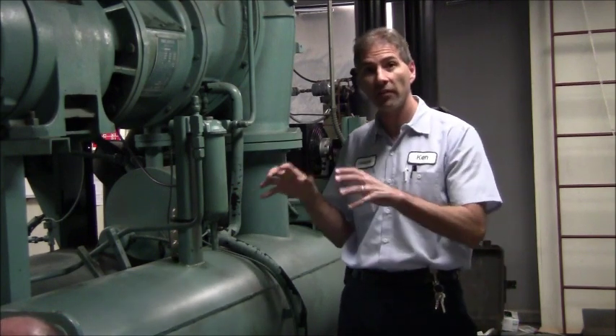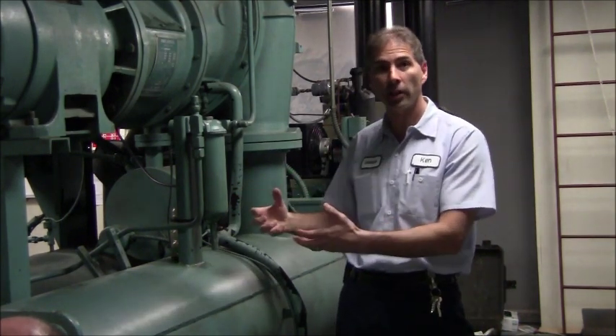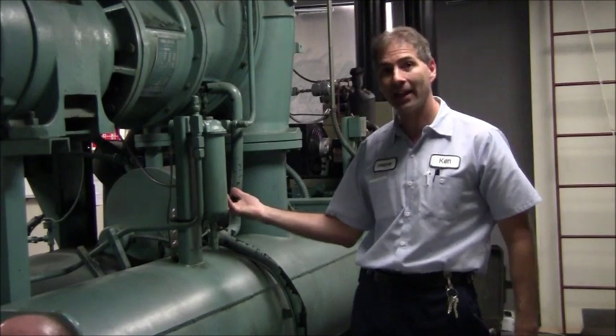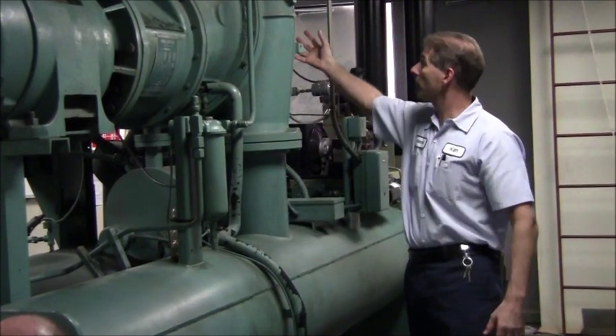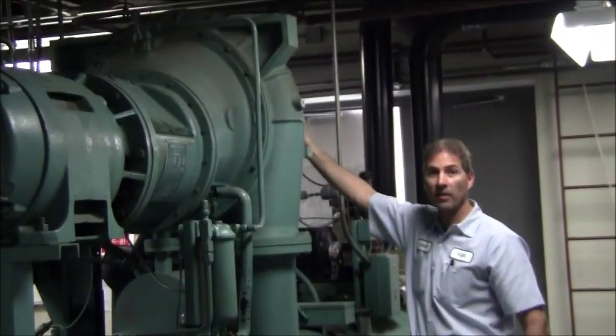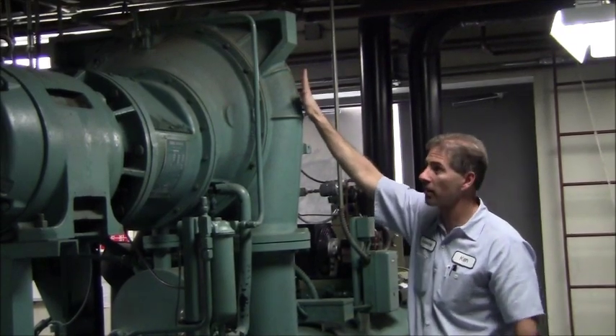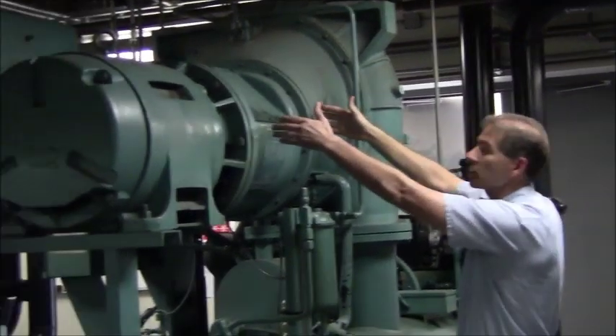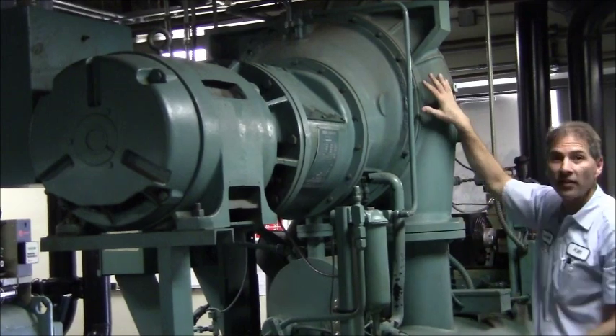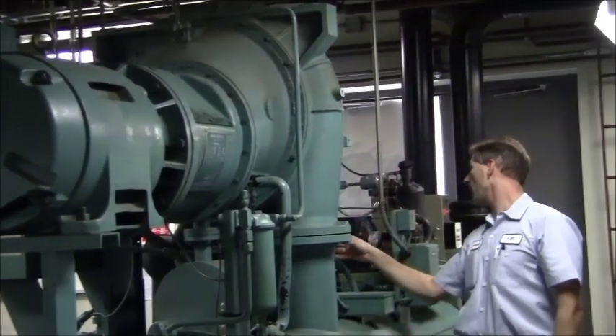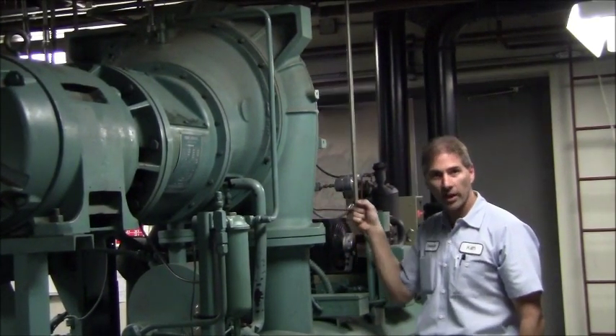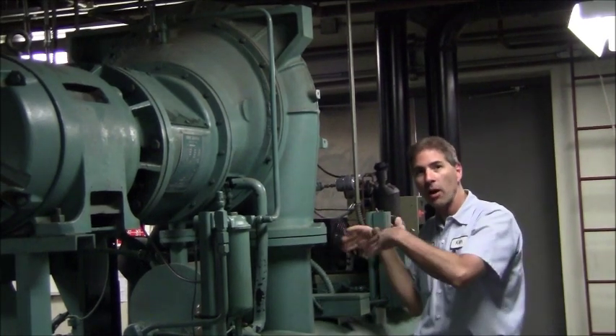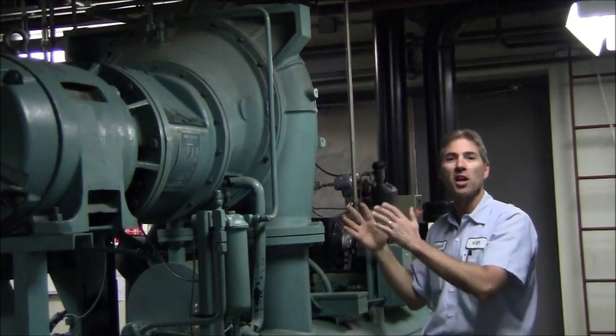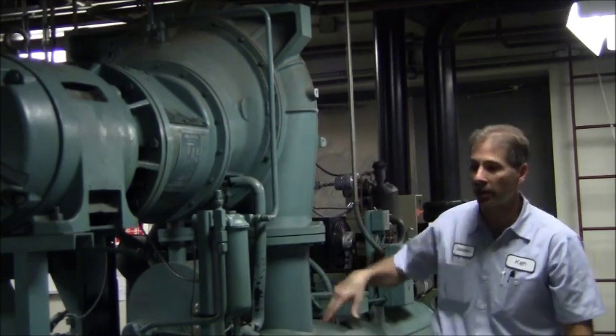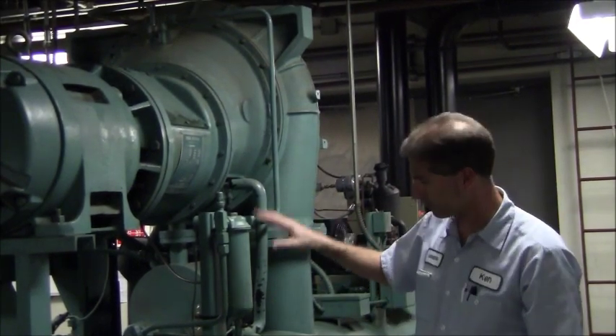The chilled water will give up its heat to the refrigerant, boiling off the refrigerant, turning it back into a vapor, where it travels to the inlet side of the impellers on this large compressor right here. Here's the motor. This is a coupling in between, which is driving the impeller. There's a gearbox over here, which operates a set of vanes to allow the flow of refrigerant to adjust the load of the refrigerant. So that's how the chiller kind of operates.